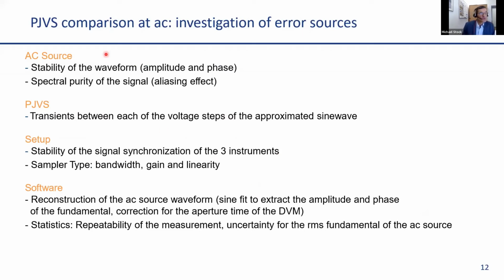Of course, to be able to do this, we need a very high quality AC source, which serves as a sort of transfer standard between the two sampling experiments. This source needs to have a high stability of amplitude or phase and a good spectral purity to eliminate the aliasing effect. Now, of course, a programmable Josephson standard, when it produces a stepwise approximated sine wave, has transients between each of the voltage steps.